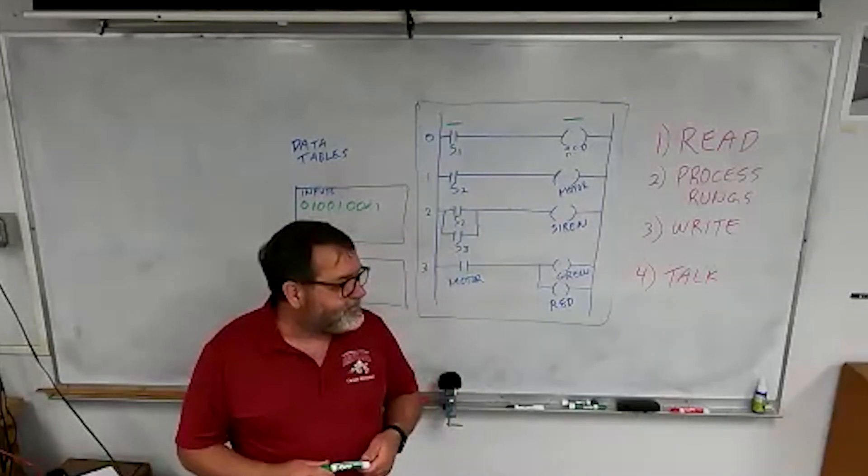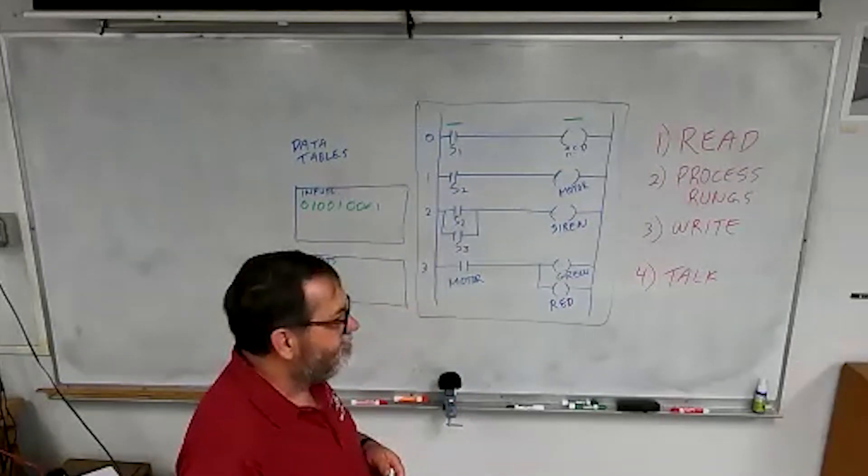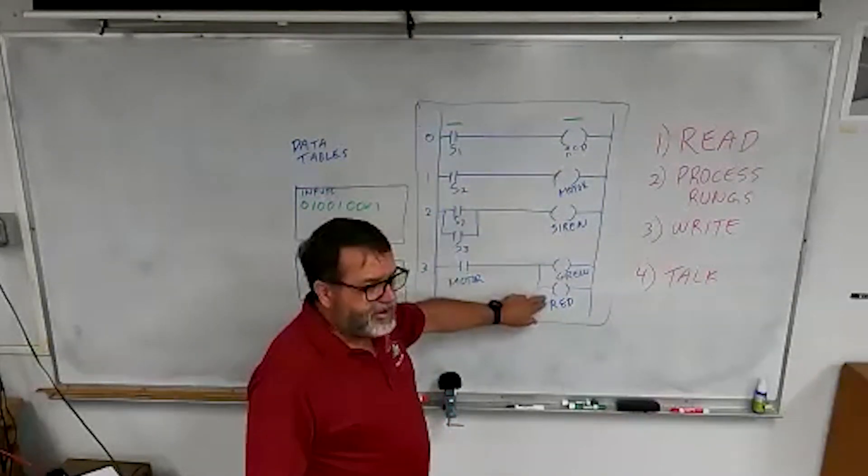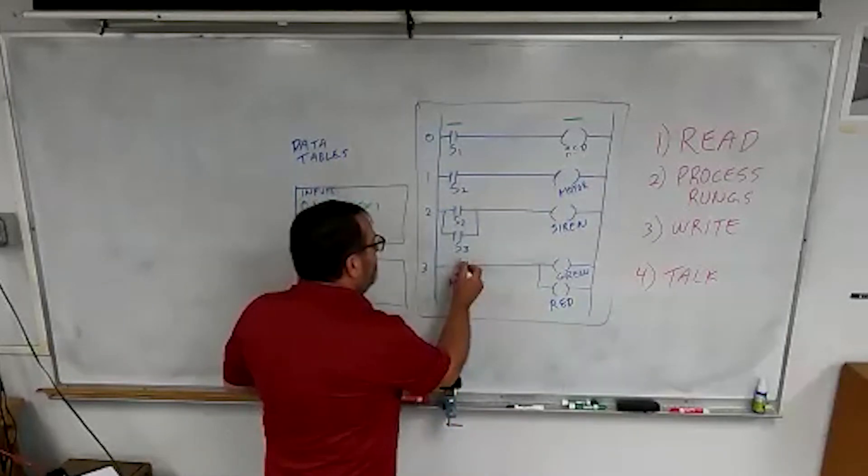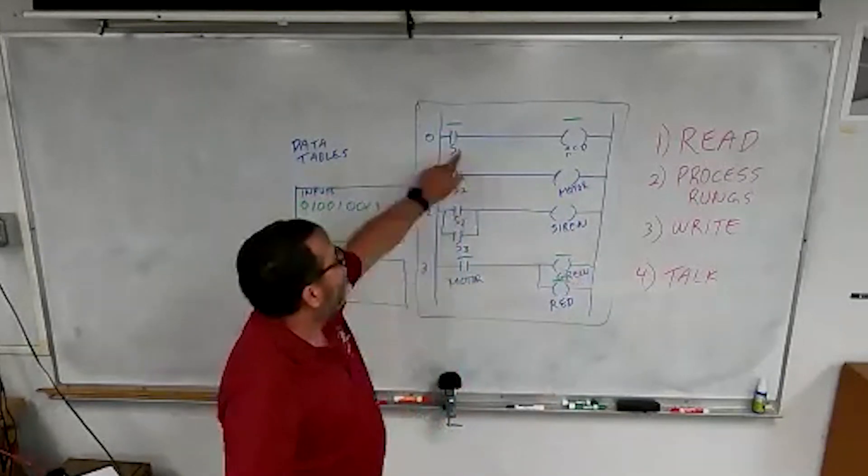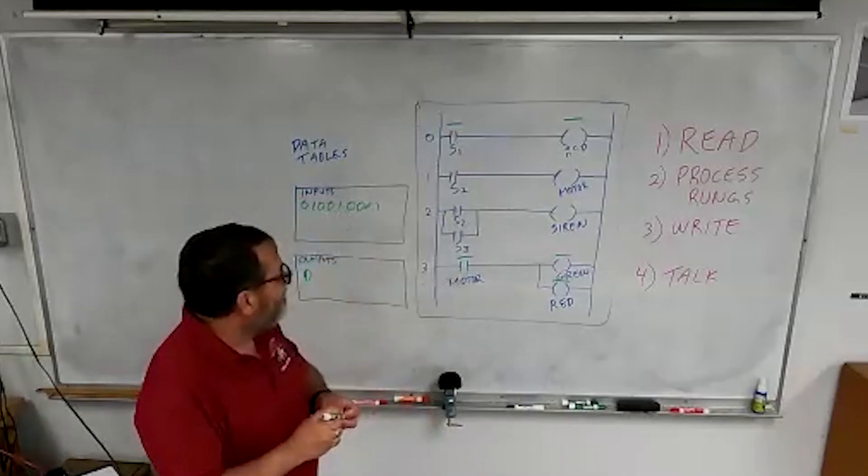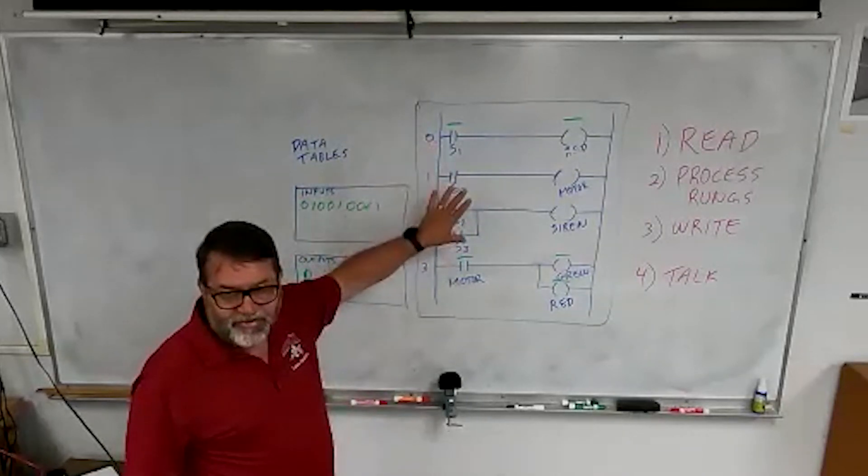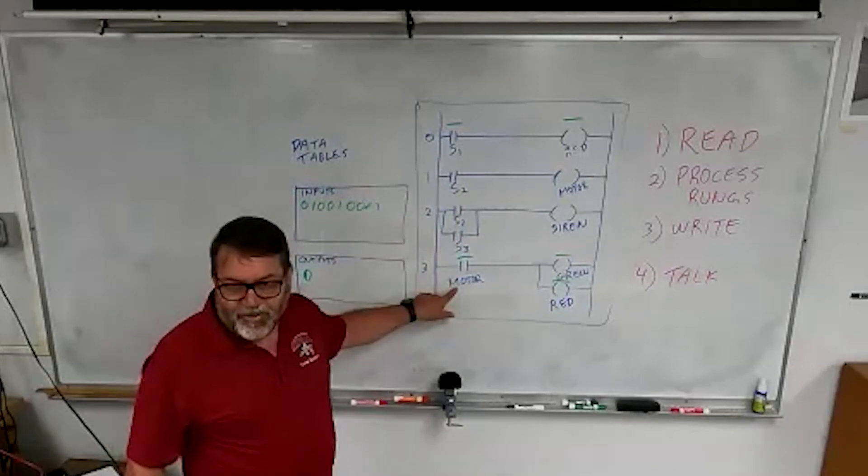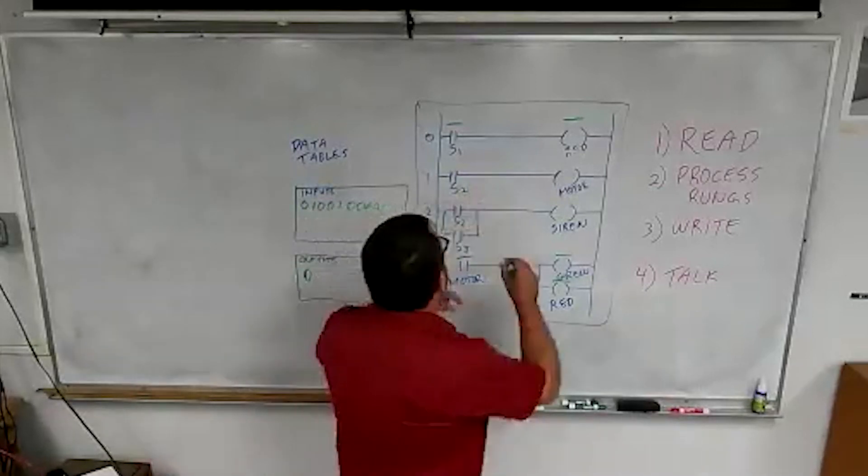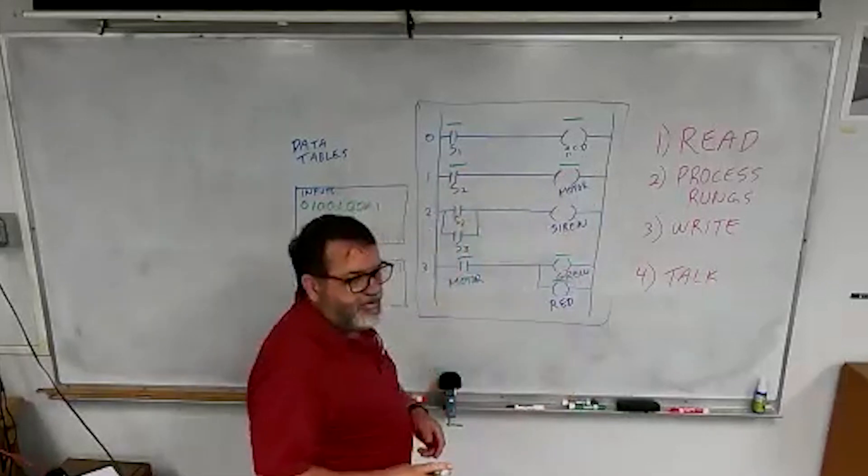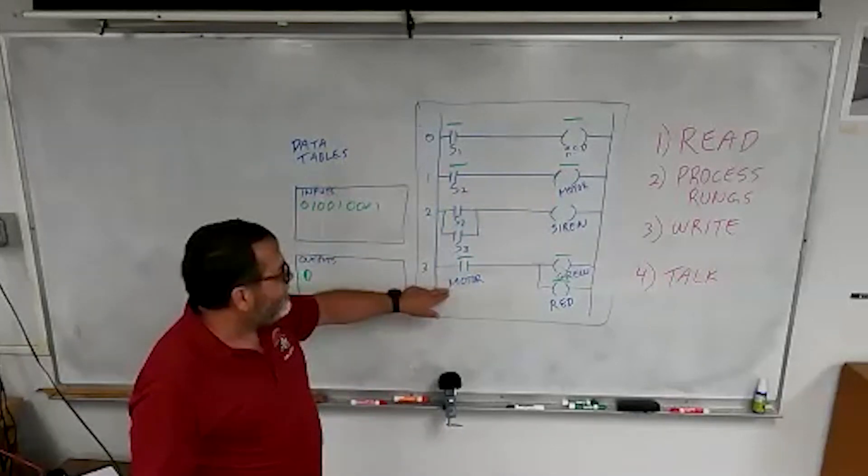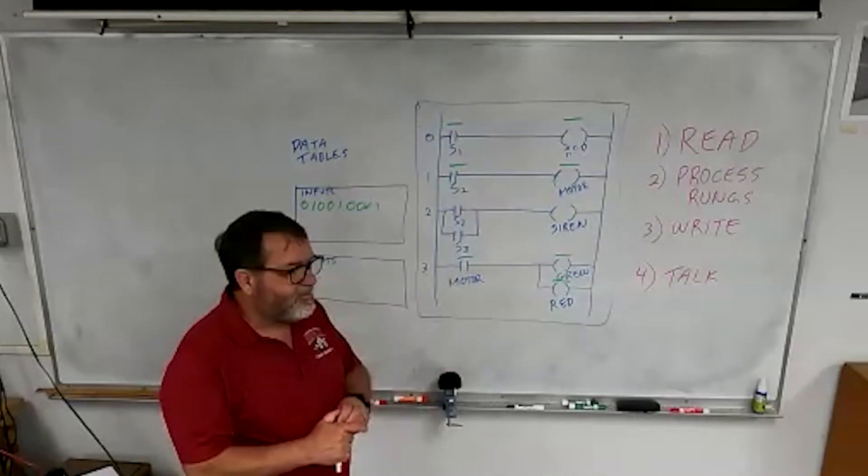So if the top one, if the top red is powered up, it'll be red. But if both of them are powered up, it turns off or it never turns on. It's never going to turn on because no matter what you do up here will get cancelled out by what happens down here. So if this motor is running, then the red light and the green light will be on no matter what I do with this switch. And so I kind of snuck this in too. Here I've got inputs, a bunch of switches. They're sending signals to my PLC. But on this last one, I said I want to use this motor as an input. Well, motors an output, it's over here. So if I turn on switch two, my motor should start. And what I'm doing in my program, I'm saying is if this motor is running down here, I want to turn on the green light and the red light. So I'm using the output as an input.